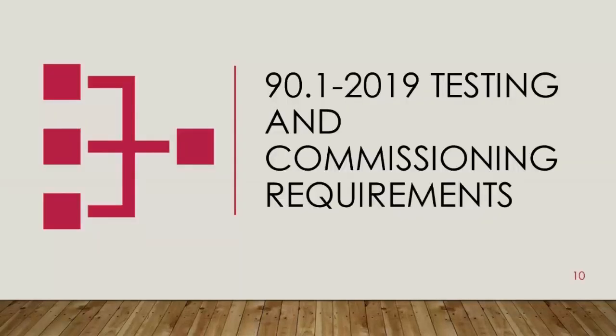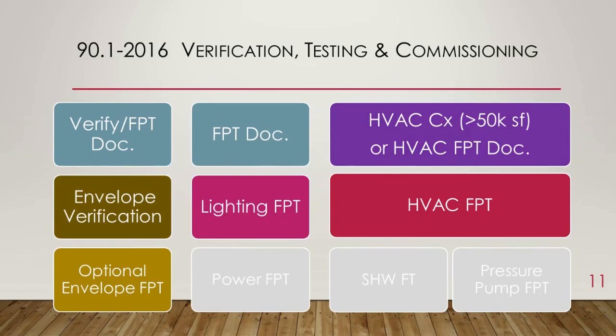So let's talk about 90.1 2019 testing and commissioning requirements. Well, first we should look at what existed in 2016 ahead of time. We did have some functional performance testing and verification documentation requirements. We had some envelope verification requirements. There was an optional envelope leakage testing that was an option to doing more detailed verification. There was separation in the disciplines of how you documented the functional performance testing. There was lighting functional performance testing and HVAC functional performance testing, although frankly it was one sentence and a little bit vague.